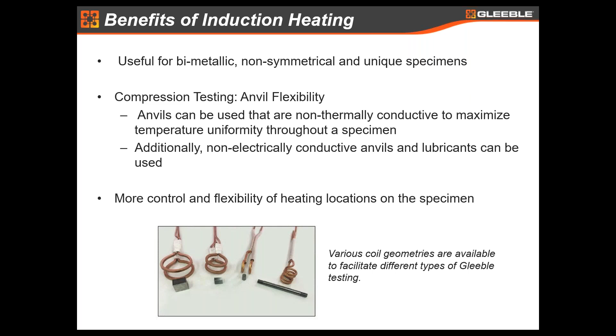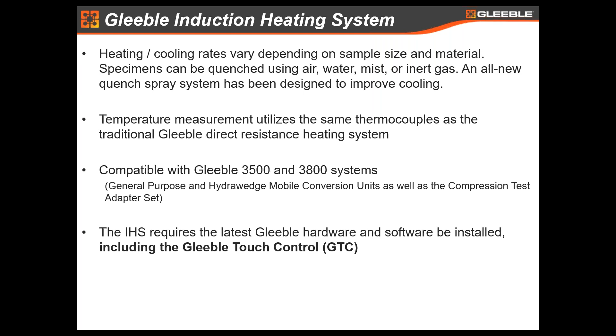So of course, heating and cooling rates will vary depending on sample size and material. I can't share today all the heating rates and all those different characteristics, but as always, we can quench using air, water, mist, or inert gas. And we have also introduced a new quench spray head system that can improve cooling as well. We use thermocouples as always to measure temperature. This is compatible with 3500 and 3800 systems, but it does require the Gleeble touch control unit. As I mentioned before, going forward, a lot of our systems will focus on the GTC.